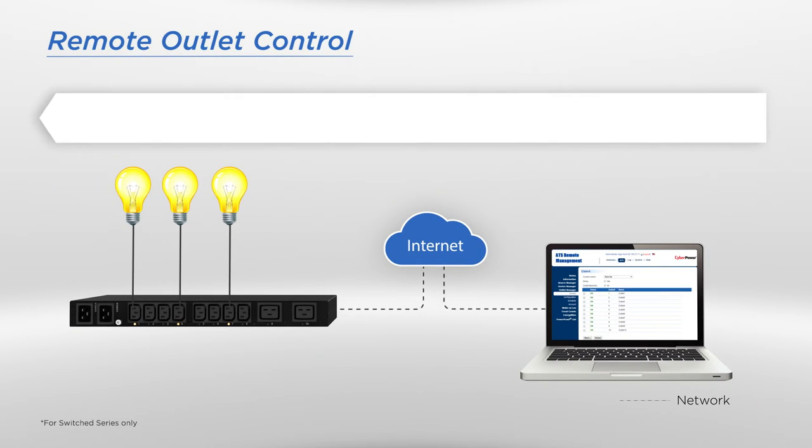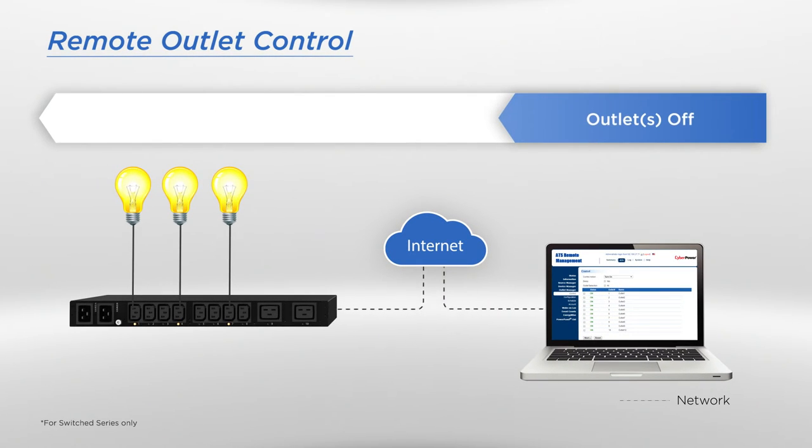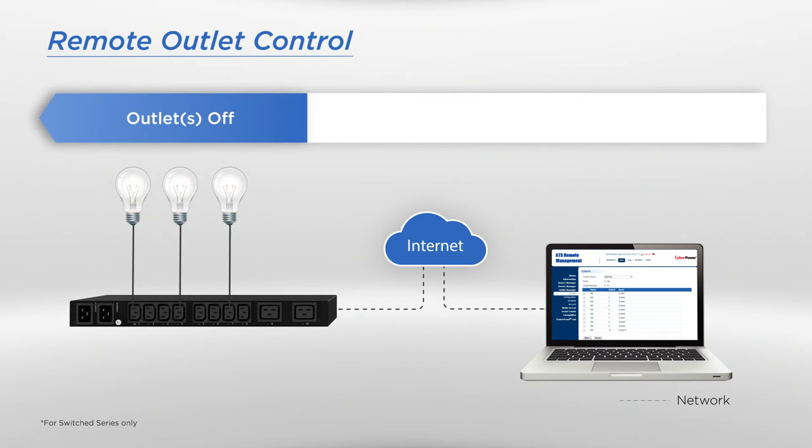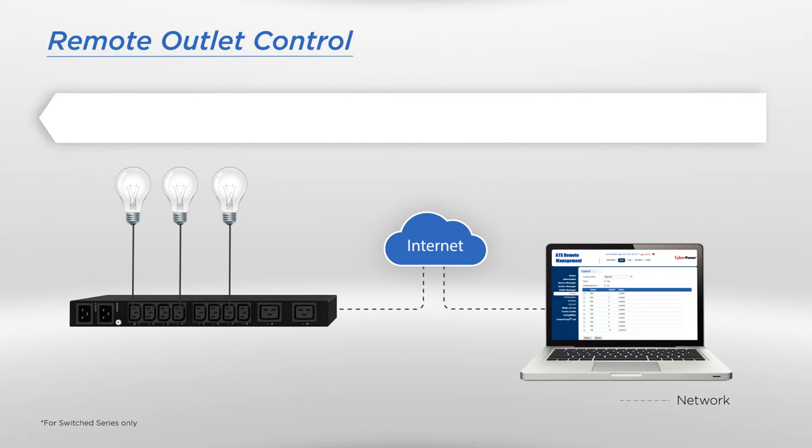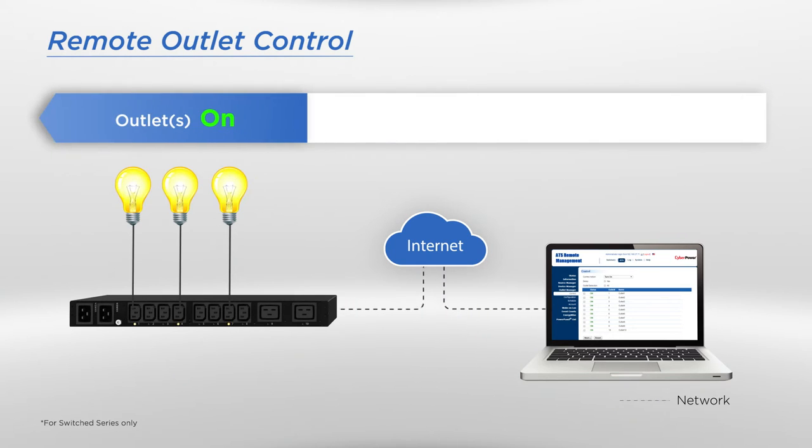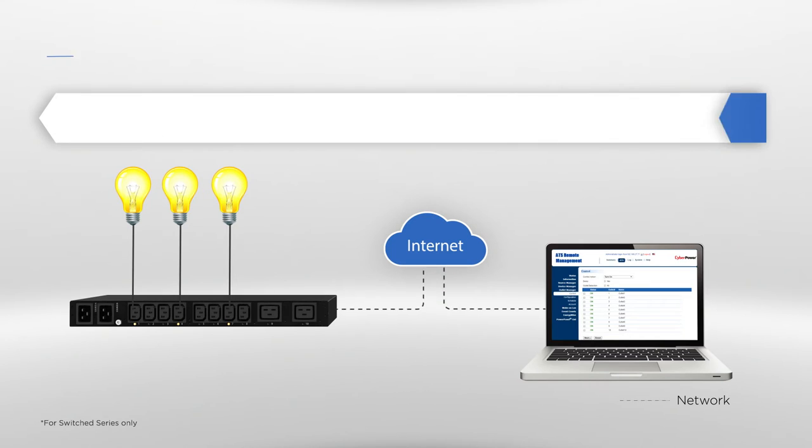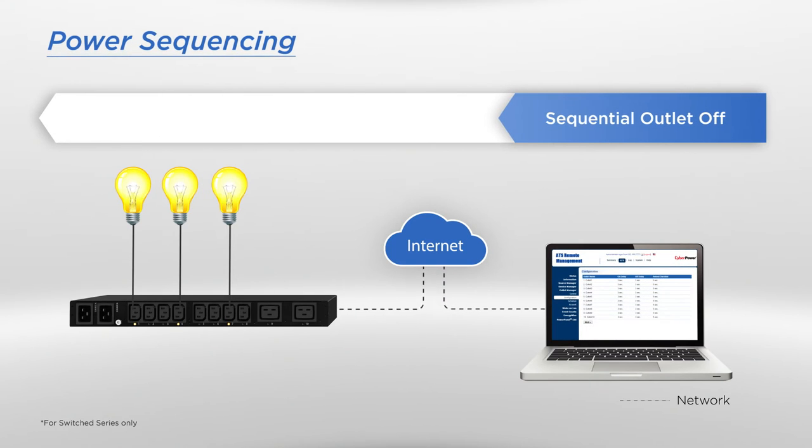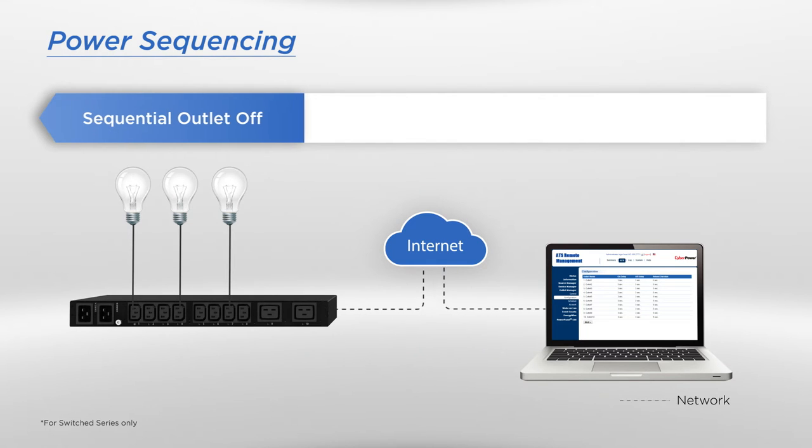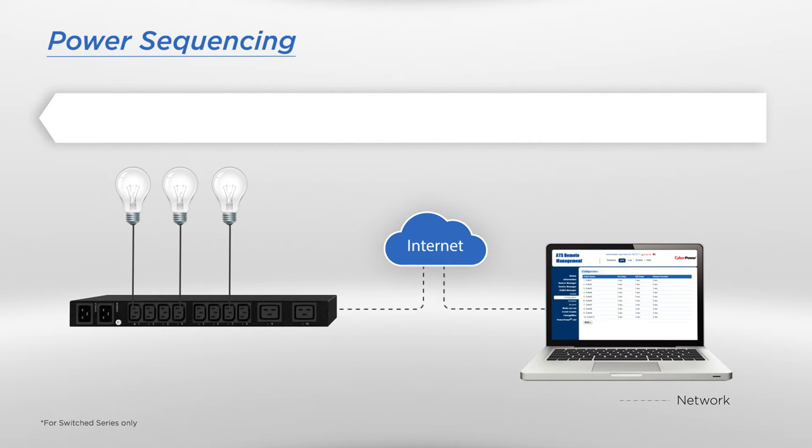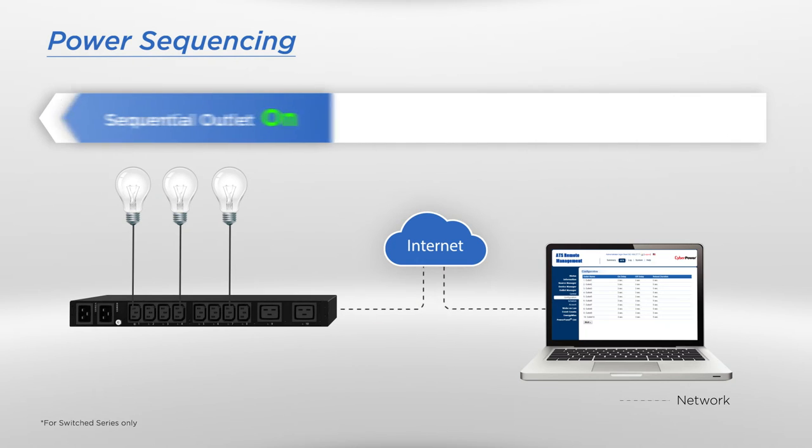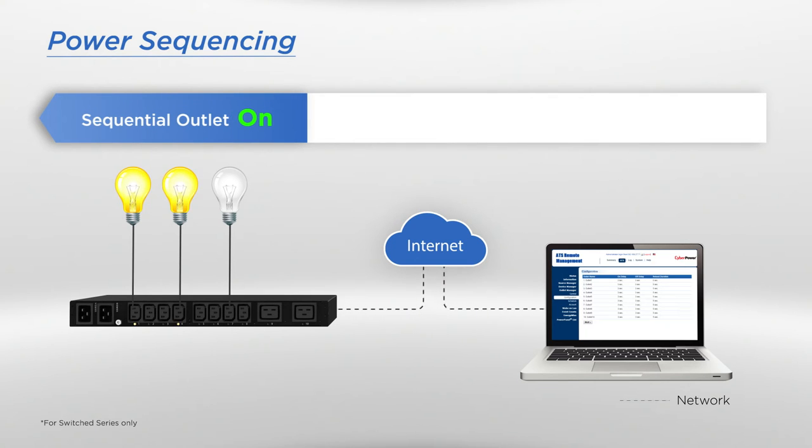Switched series especially features remote outlet control to reduce on-site visits, allowing you to turn it on, off, or reboot the outlet individually or collectively anywhere. Furthermore, switched series gives you the option to determine the order in which the outlet turns on or off. This feature is best used to avoid in-rush current as outlets are able to switch on by sequence instead of all at one time.